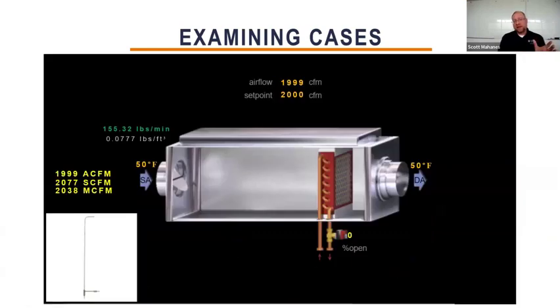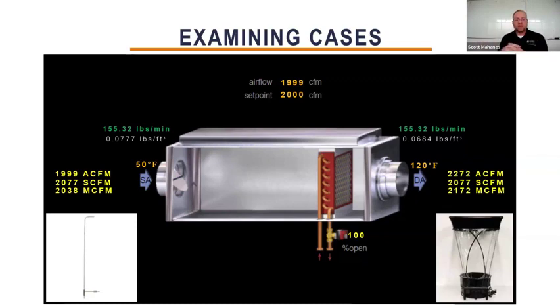So going back to this VAV, if I happen to have an open reheat coil and I go to 120 degree discharge, well, my density's changed. But what doesn't change is mass. We've talked about how that's a law, that it stays conserved. So if mass stays the same and density goes down, the volume goes up.